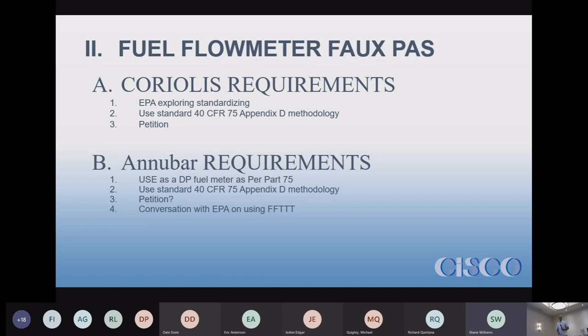you can calibrate the Coriolis meters according to the Part 75 standard, where you compare it to inline flow, or send it out to have it compared against flow from something else. And you don't need the petition, but if you want to use it based on its own technology, you're going to have to petition. And every time you petition them, it will go through. I've been involved with 3 or 4 petitions so far, and they've gone through without issue. Even the EPA, I think, is in the midst of finally standardizing these.